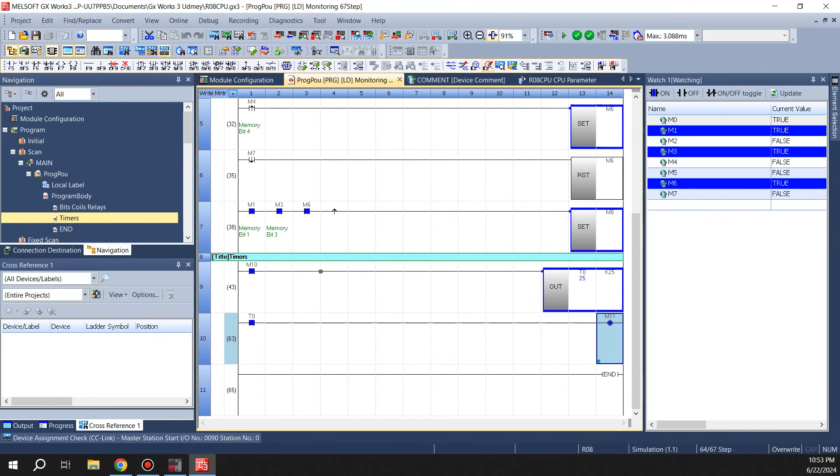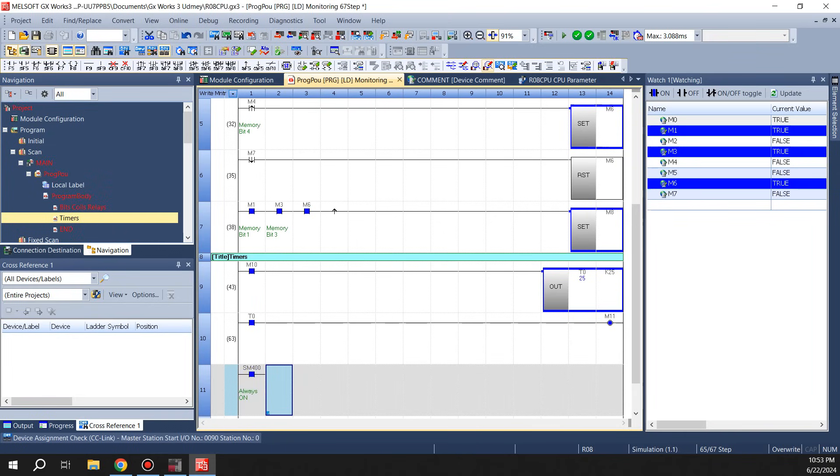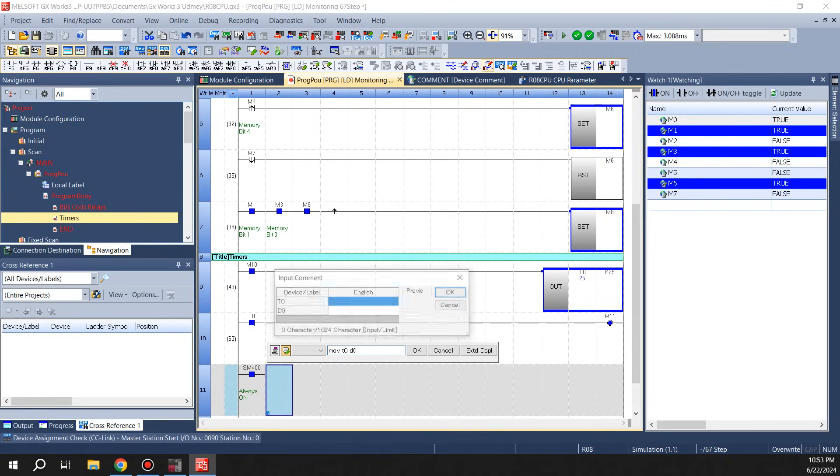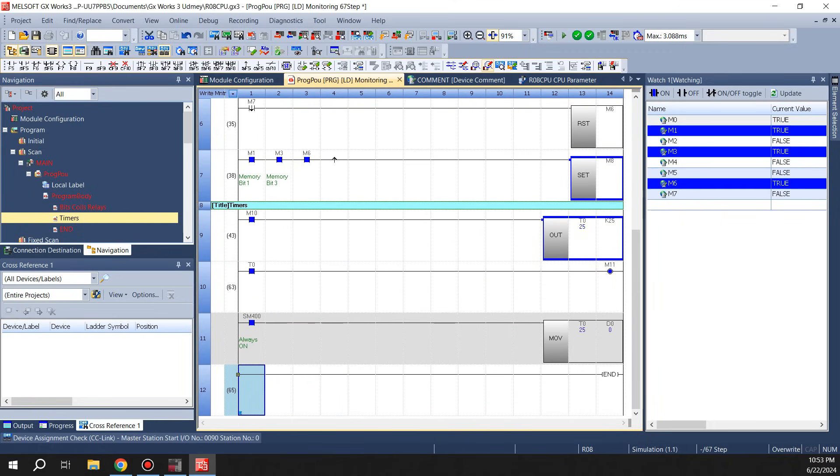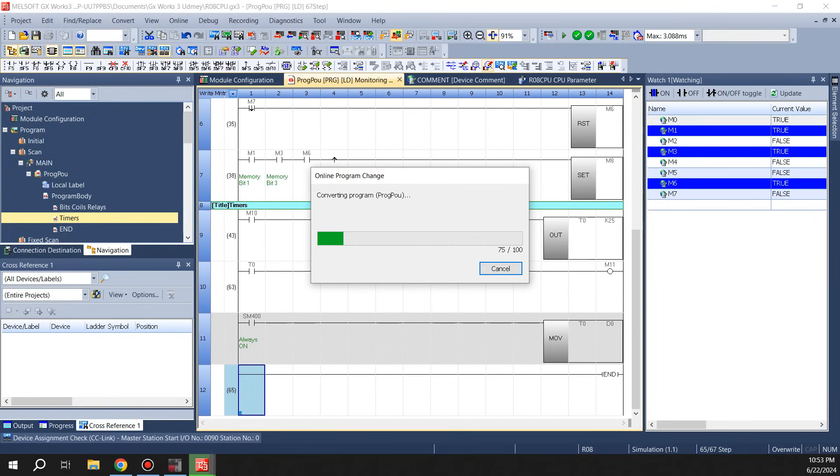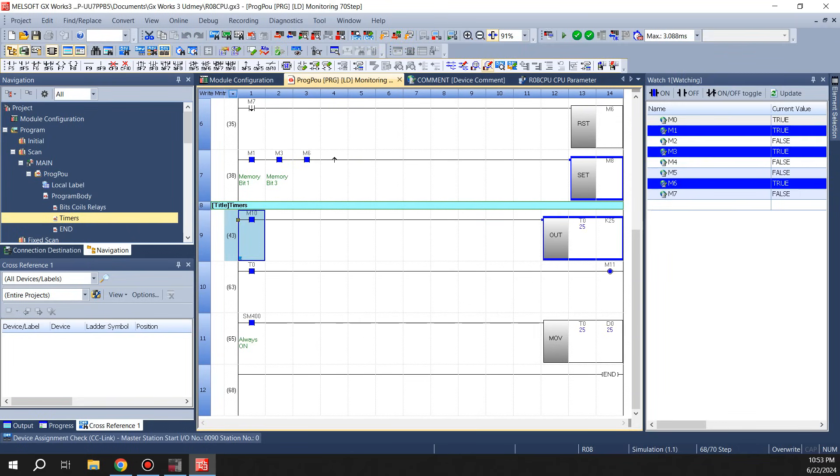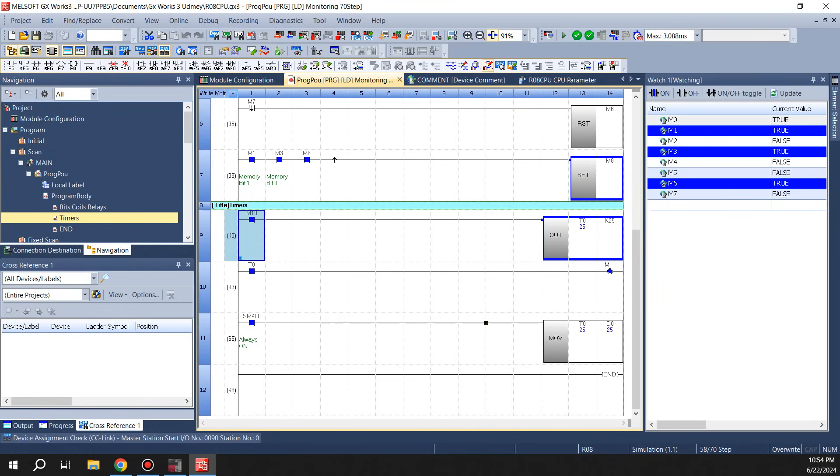Also you can move the timer value into a D register if you want to use somewhere or display on the HMI. It's pretty straightforward. What we can do is use SM400 which is an always-on bit, move T0 into D0. It's that simple. So now it's always going to move the timer value into D0. So here, turn it off, turn back on, there you go. That's how you can make it start timing and move the value. So that's how you use timers in Mitsubishi IQR PLC.